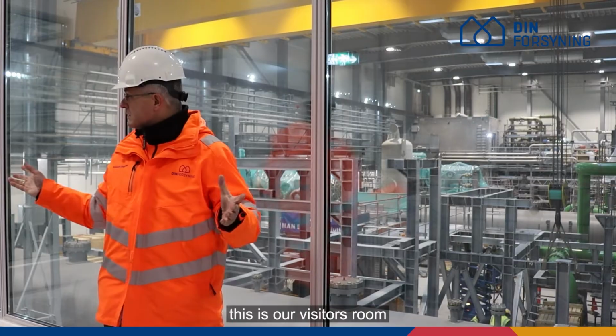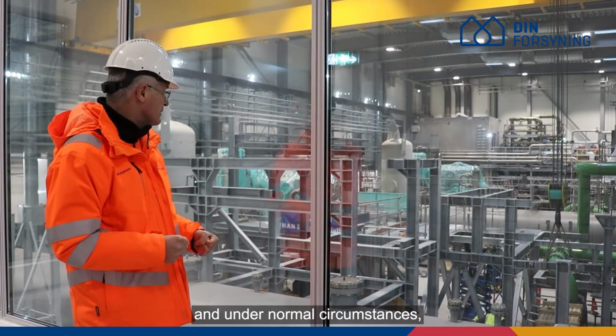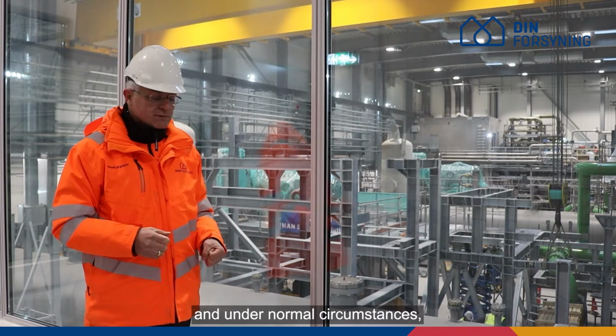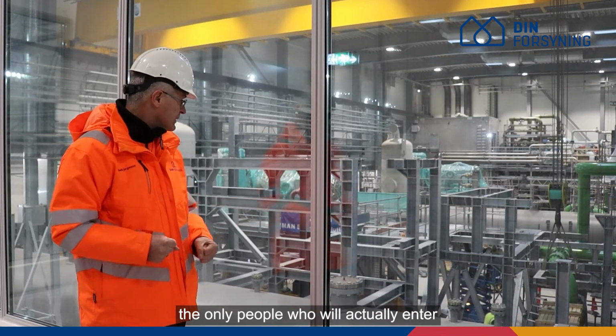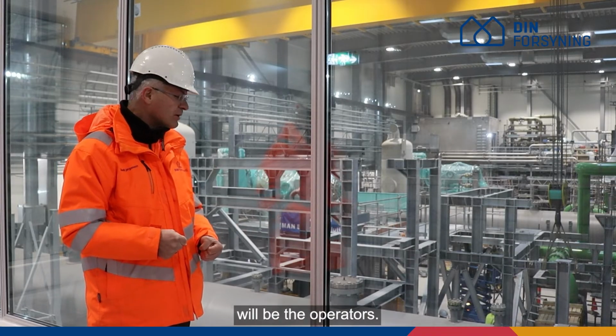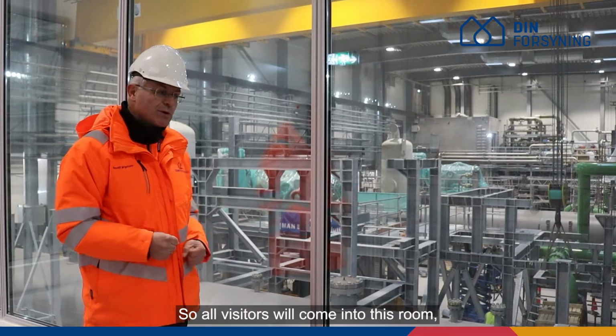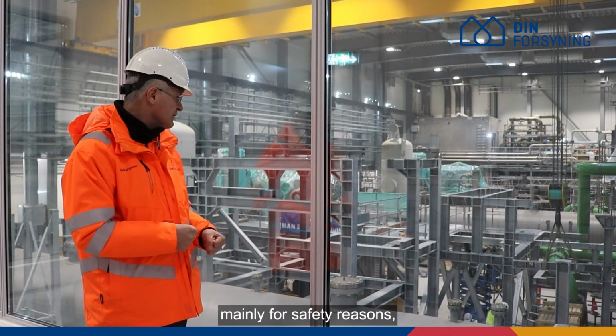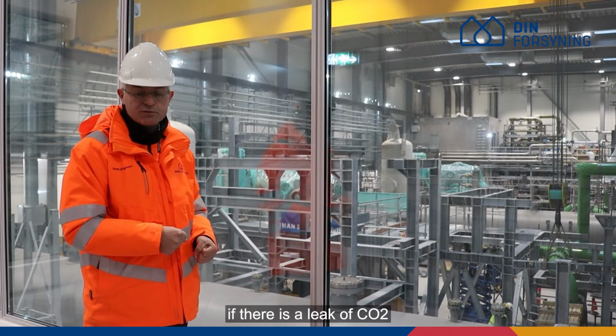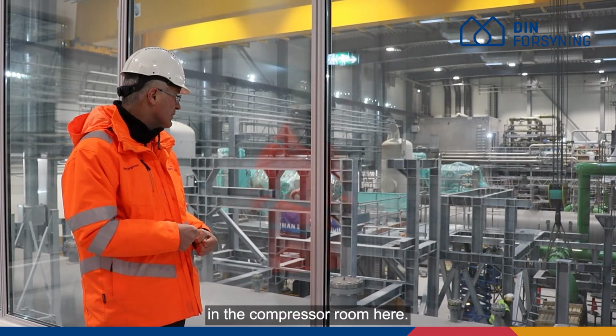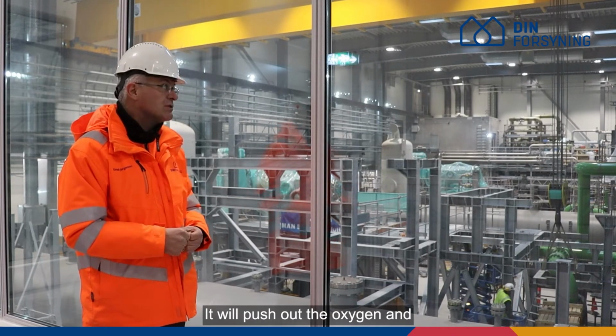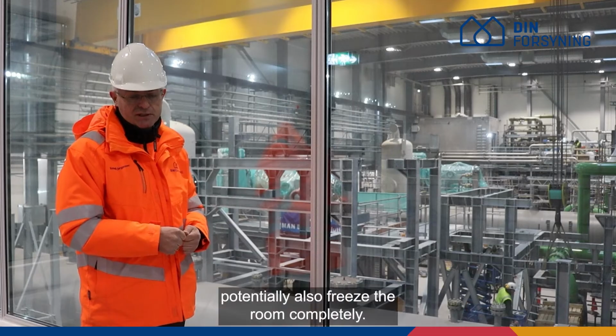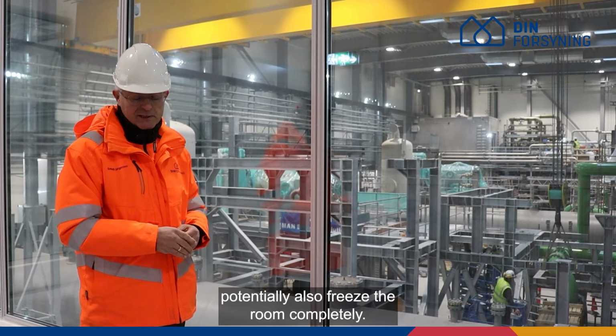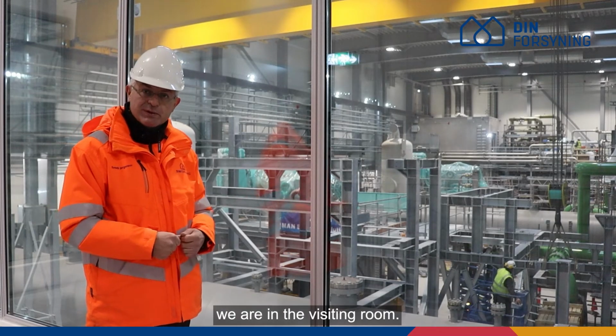We are here, actually, this is our visitors' room, and under normal circumstances, the only people who will actually enter the compressor room here will be the operators. So all visitors will come into this room, mainly for safety reasons. If there is a leak of CO2 in the compressor room here, it will push out the oxygen and potentially also freeze the room completely. So for safety reasons, we are in the visiting room.